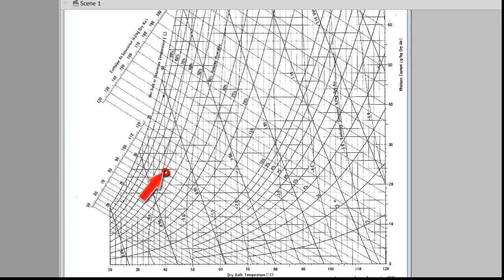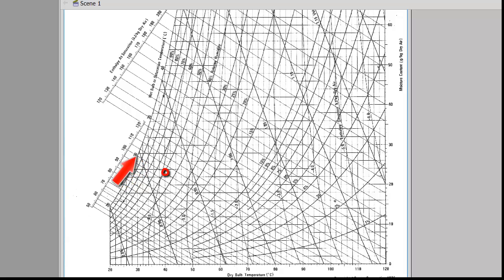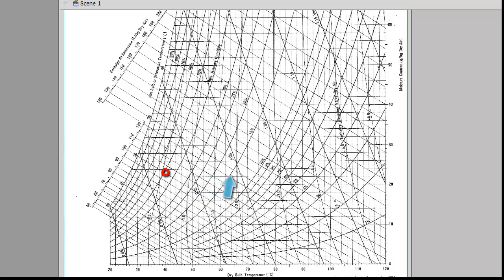For the enthalpy, we follow the constant enthalpy line — which is the same as the wet bulb temperature line — and read that value as 100 kilojoules per kilogram dry air. For humidity ratio, we follow the horizontal line to where it meets the right-hand axis and that value is 23 grams of water per kilogram of dry air.